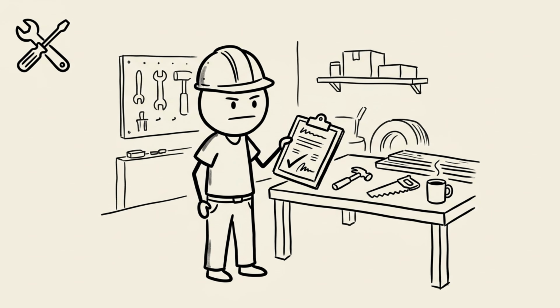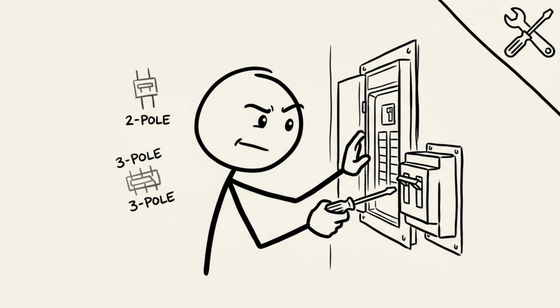Phase 1. Design and permit before a single wire is touched. A licensed electrician runs the load calculation and pulls the permit. Homeowners are generally not permitted to self-install a battery-based energy storage system. Phase 2. Mount the backup subpanel and the transfer switch, and decide the grounding architecture before any wire runs. Pick this wrong, and you either create a shock hazard or a code violation that fails inspection outright.